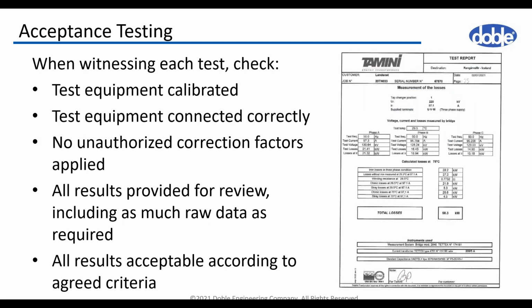When we witness factory testing, there are a few things we always want to check. This is test equipment, and particularly if it is within calibration and if it is suitable for the particular test. We also check the test connection, if it's correctly prepared, and some measuring equipment needs correction factors, like power analyzers. They need the measuring transformer ratio to show us the actual result. We check if the correct ratios are applied in the instrument. We also insist on raw measurement data from the manufacturer in order to double check the manufacturer's calculations.